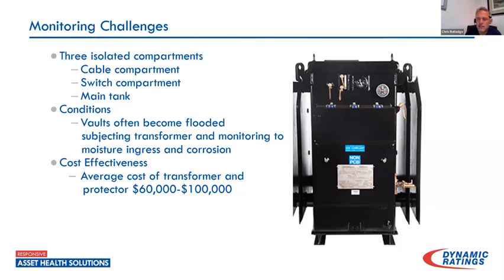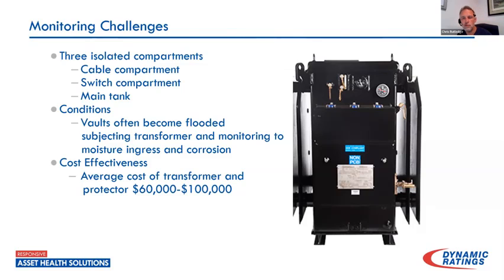With these transformers in particular, when looking at online monitoring, they're kind of unique. They have three isolated compartments — they don't share a gas phase at all. They are nitrogen-blanketed for the most part. You have a cable compartment where your primary comes into the transformer, a switch compartment which lets you isolate or ground that transformer, and then a main tank where your core and coil assembly resides.